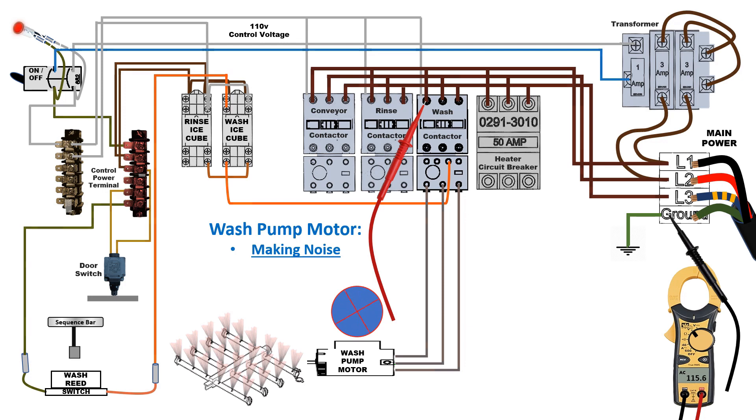To test our voltage we use a multimeter set on AC voltage, one meter lead to ground, and one meter lead to the top side of L1 of the contactor. We test the voltage at the bottom of the contactor to verify do we have the same voltage coming through the contactor. Here we're looking at L3 that's showing a low voltage of 38.5 volts. We verify that's all the volts coming out of the bottom of the contactor.